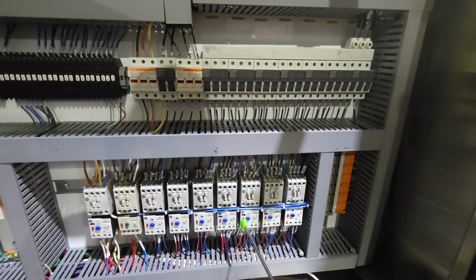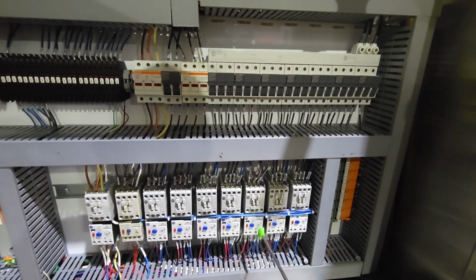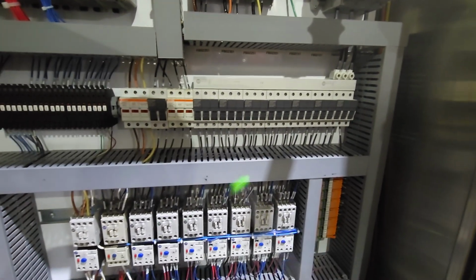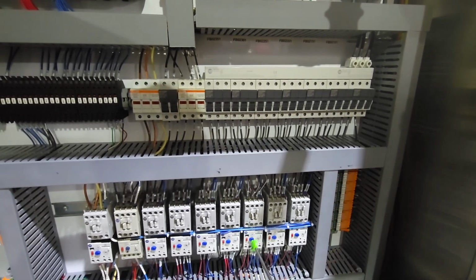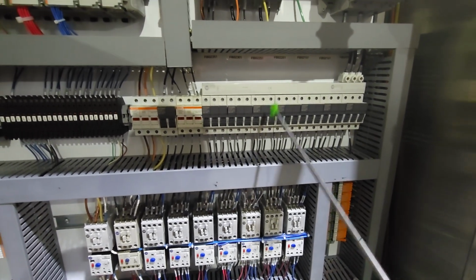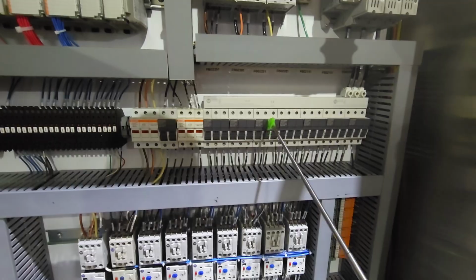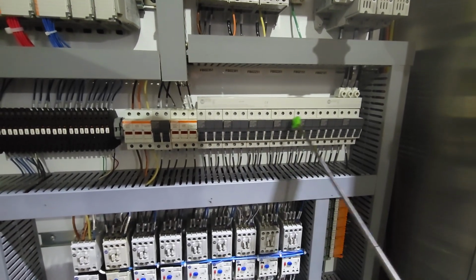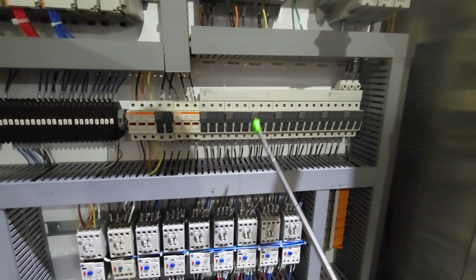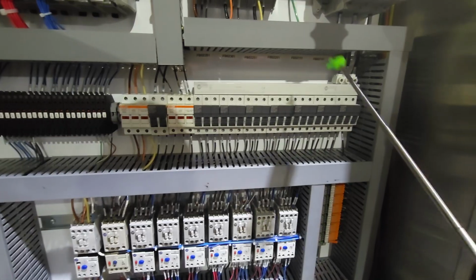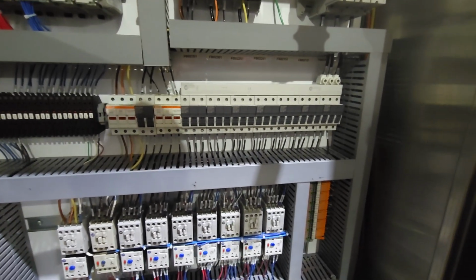So yep, you will come over here. If it's overloaded, reset your overload. If you see lights, you're going to have to pull your fuses. You do not want your contactor to be in when changing your fuses. Use your palm safe fuses. You can pull them down, but technically you should just turn it off.